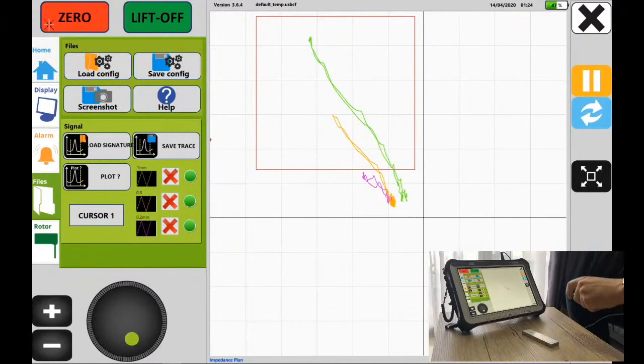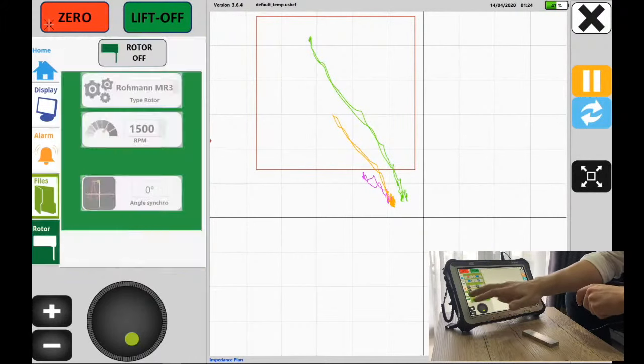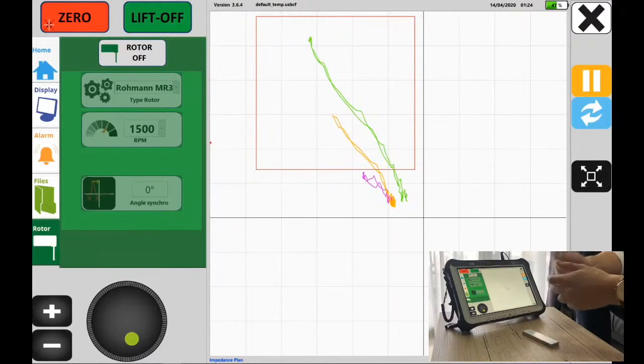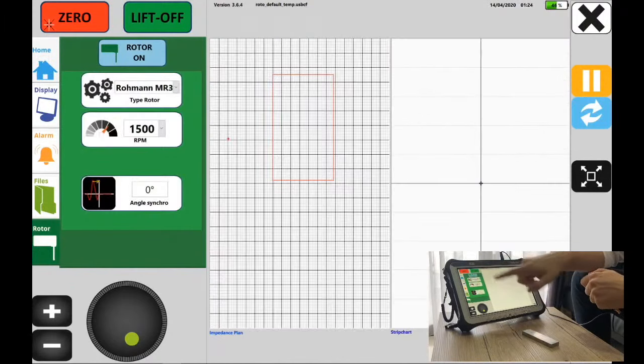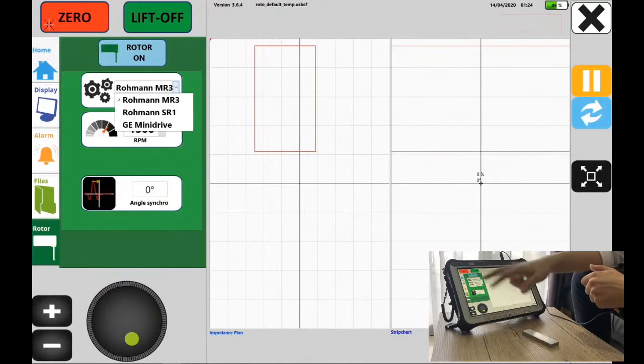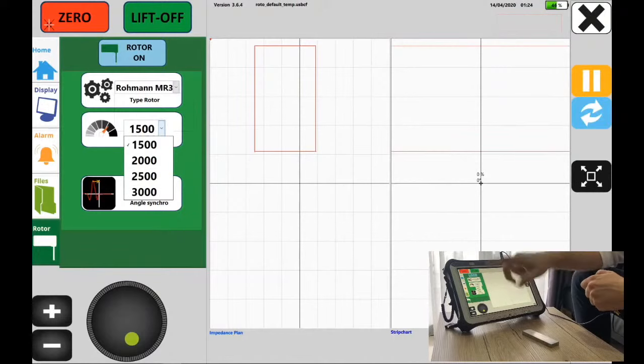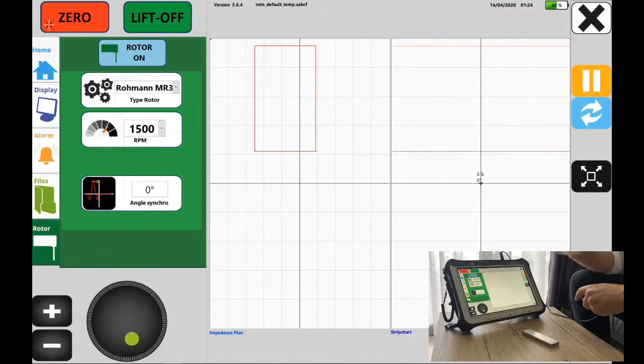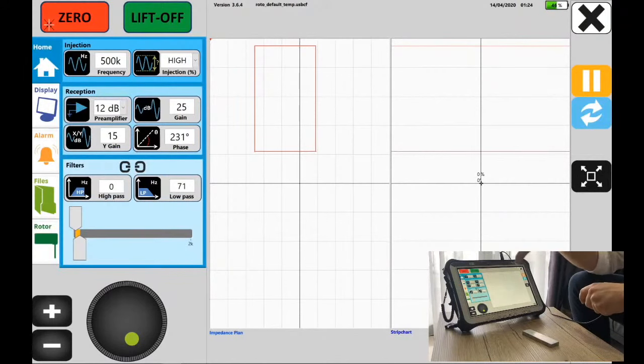This conventional eddy current module also has roto test capabilities. To use that, I'll have to change the cable and the probe to use a rotating scanner, turn it on, select which scanner I'm using, set the right speed of rotation, then go back to the setup window and set up all the right parameters to do the job, exactly as described before for conventional ET, but this time for roto test.